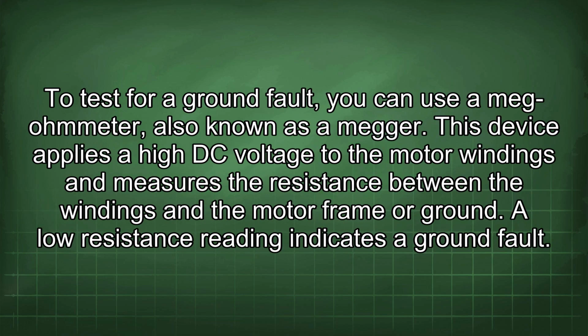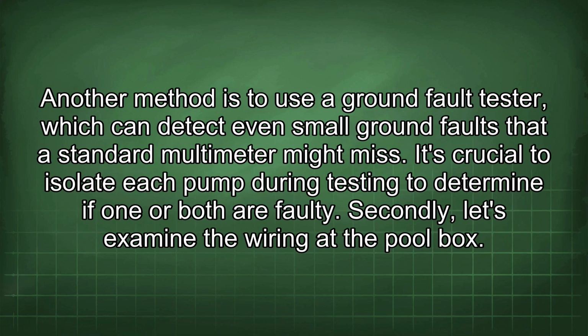To test for a ground fault, you can use a megohmmeter, also known as a megger. This device applies a high DC voltage to the motor windings and measures the resistance between the windings and the motor frame or ground. A lower resistance reading indicates a ground fault. Another method is to use a ground fault tester, which can detect even small ground faults that a standard multimeter might miss. It's crucial to isolate each pump during testing to determine if one or both are faulty.